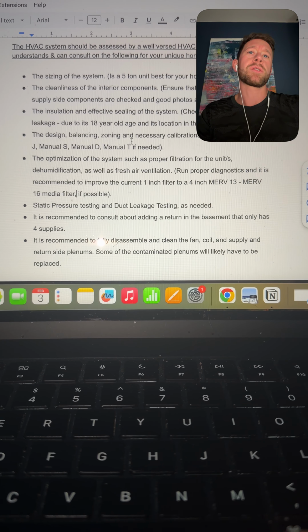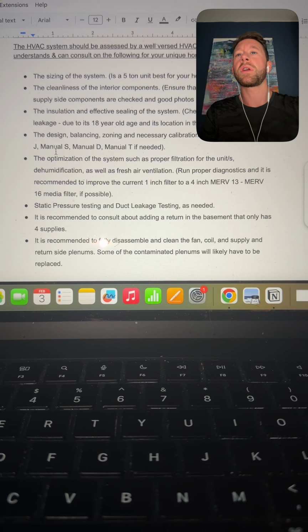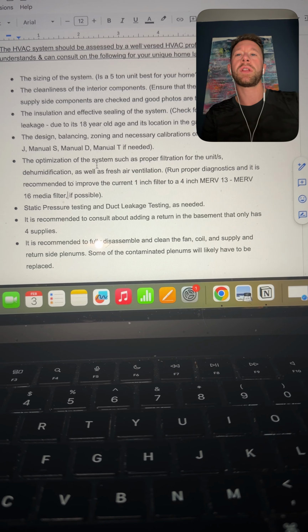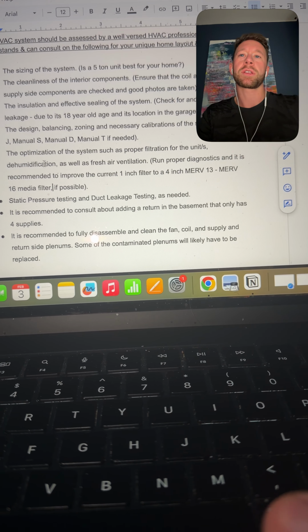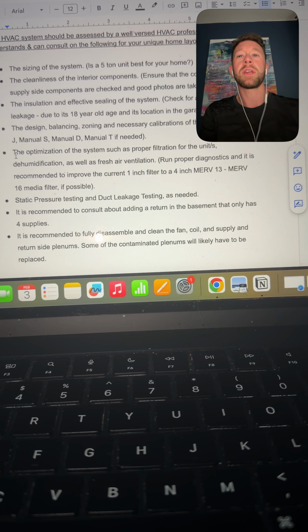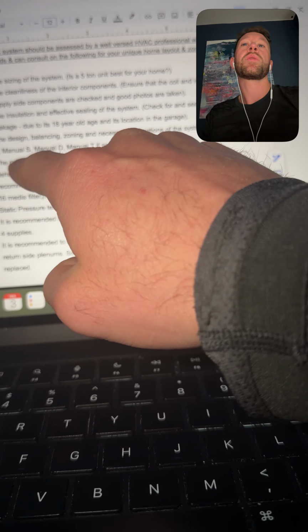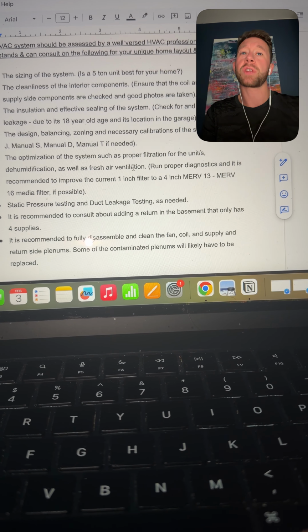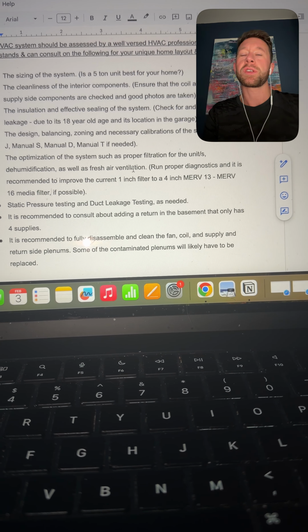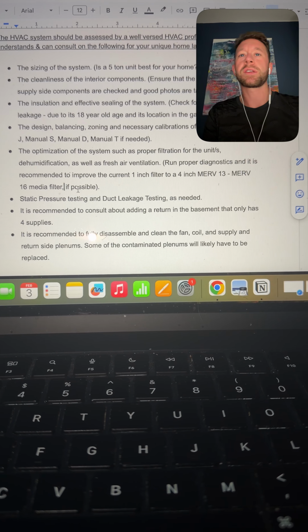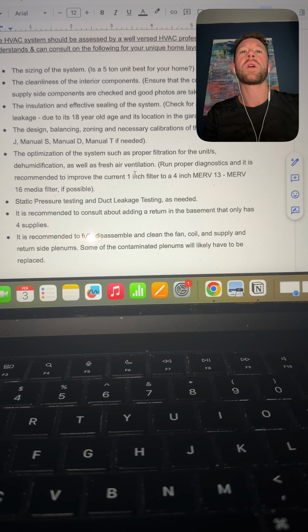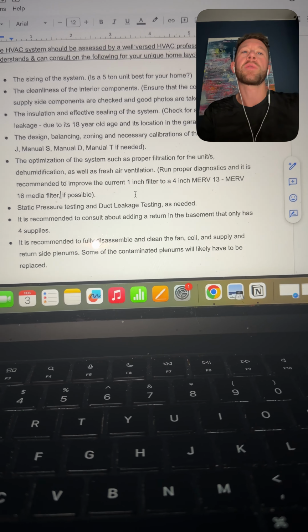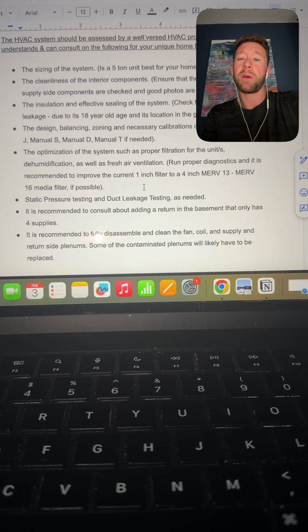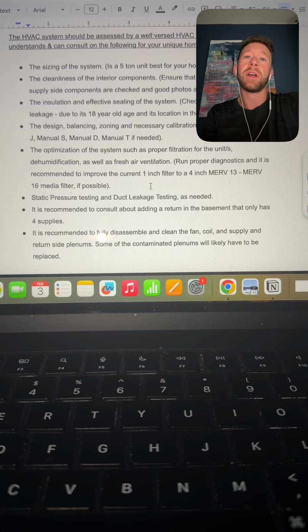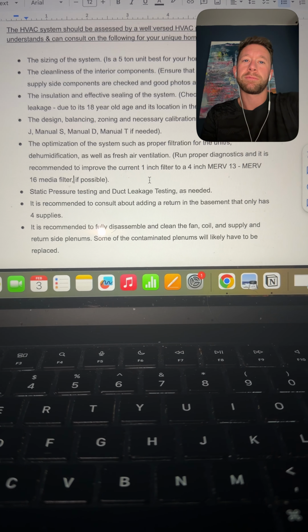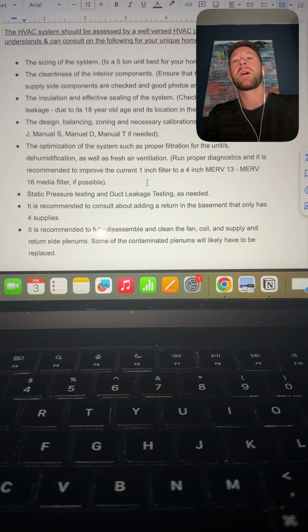The design, balancing, zoning, and necessary calibrations of the system. This could be Manual J, Manual S, Manual D, Manual T if needed. That's a massive project in itself that might not be needed here, but the next would be the optimization of the system for the proper filtration, dehumidification, and potentially fresh air ventilation as needed. So they've got to run proper diagnostics and recommend to improve the current 1-inch filter with a 4-inch MERV 13 or MERV 16 media filter. So that one system has been dealing with a 1-inch filter. It's not the right one for best air quality for their home.